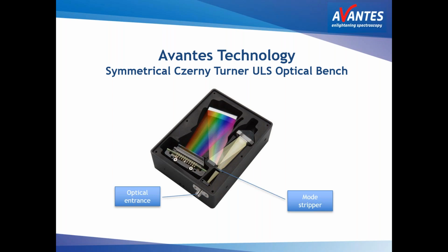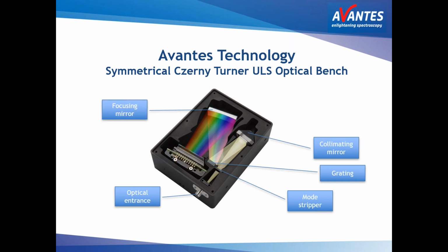The light then goes through a mode stripper to reduce mode effects and will transmit onto the collimating mirror. This then collimates the light onto the grating, which will act as a prism to disperse light onto the focusing mirror. And then the focusing mirror will send the light onto the detector. Before it hits the detector, there may be some order sorting filters, maybe some blocking filters. We can also do some lensing before it hits the detector array. It just depends on the configuration and your application.